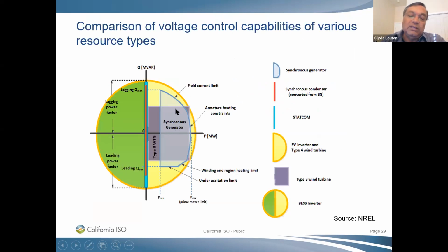This plot here is looking at the capability. So again, you saw a version of this back in the solar test, where the synchronous machine can provide this area of support. Inverter-based resources can give you a lot more support, both in the leading power factor range and also in the lagging power factor range. So you get a lot more reactive capability or control capability with inverter-based resources. My job here was to really look at the capability of these resources, but it is eventually going to come down to economics and who gets paid for providing what services. But again, the inverter-based resources out there do have the capability to provide essential grid services, which is what we really need to eventually migrate to a carbon-free grid.